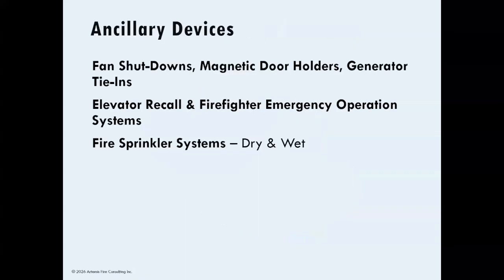And our final component is the fire alarm ancillary devices, which are extra components or relays that are attached to and work with the main system for fire life safety, but are not part of the fire alarm system itself. They include a long list of items which perform tasks like releasing locks, venting smoke, guiding elevators, or notifying hearing impaired people when an alarm triggers. Not all buildings will need to have these devices, but when you do, they must be interconnected with the fire alarm system and their correct operation confirmed by integrated system testing on a scheduled basis. We'll get into more of that shortly.